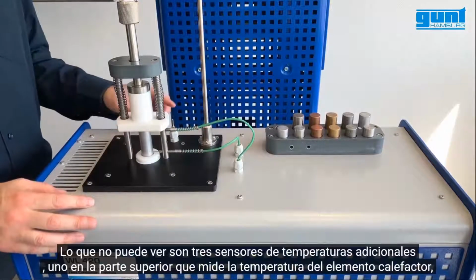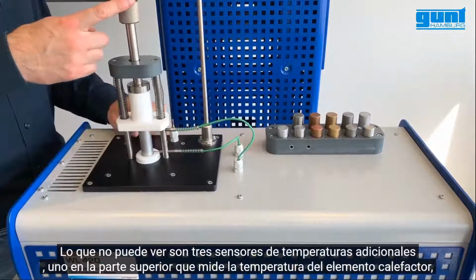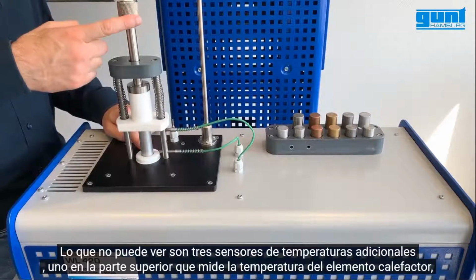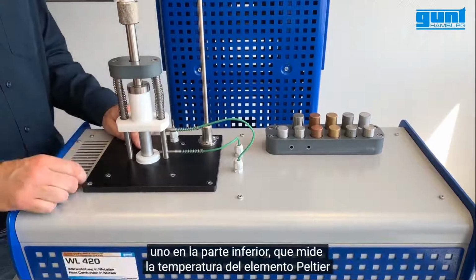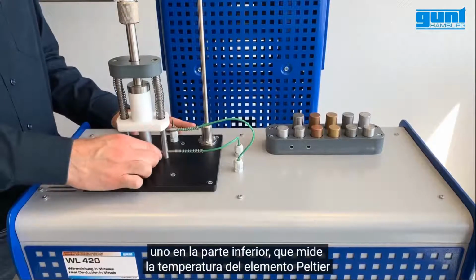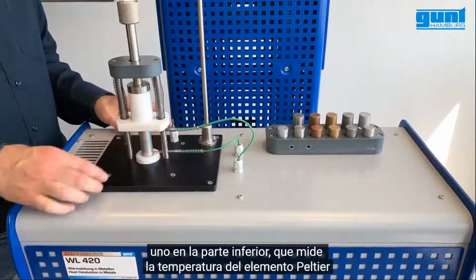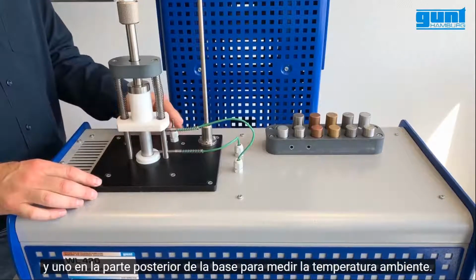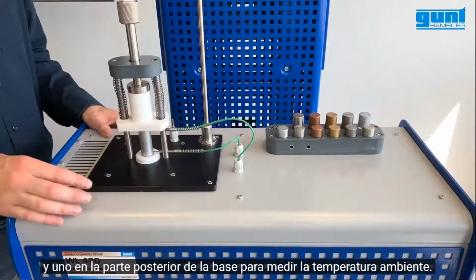What you cannot see are 3 additional temperature sensors, one in the top measuring the temperature of the heating element, one in the bottom measuring the temperature of the Peltier element, and one at the back of the base for measuring the ambient temperature.